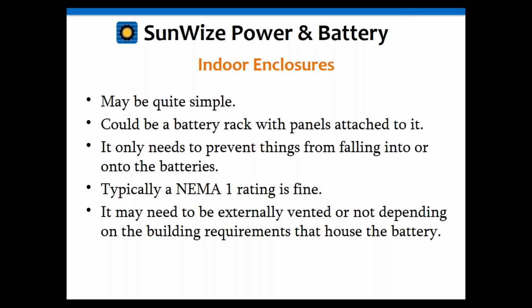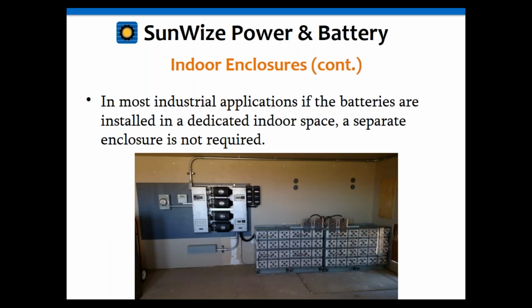It may need to be externally vented or not, depending upon the requirements for the batteries and where they're housed, such as in another building. It may also depend on the jurisdiction you're in and what the authority having jurisdiction requires. In most telecom situations like this, that's usually not going to be an issue.